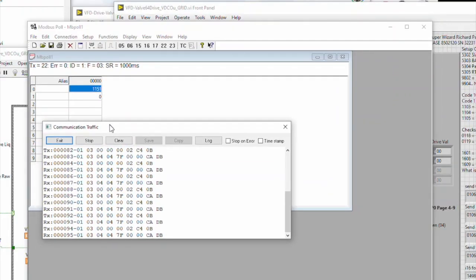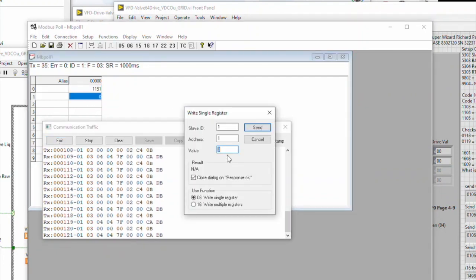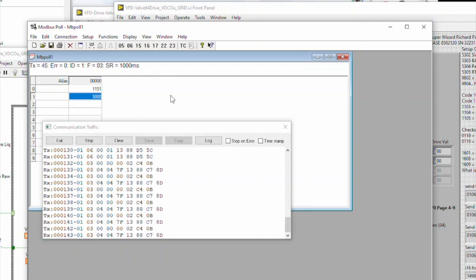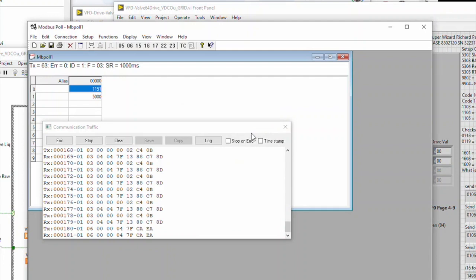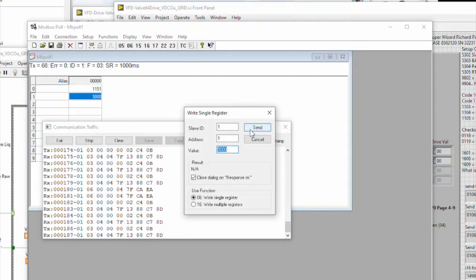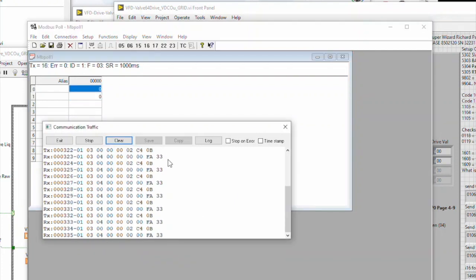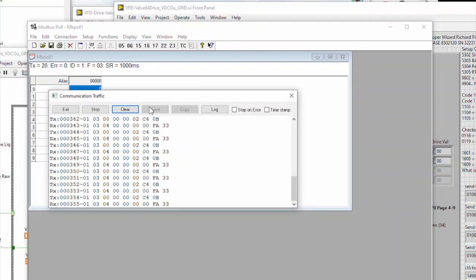And here's the communication traffic. You can see it's address 1, function code 3, and we've got a TX and an RX. And these are the CRCs. So I'm going to set this to 5,000. So we'll see that 5,000 be sent. You can pause the video and see what goodies are, and you'll see how it's set at 15 hertz. And now I'm going to set it to 0 and turn it off. Here's what 0 looks like. Some tricks to know: if you change parameters in 53 and 98, you need to cycle the power of the ACS 550, 510, whatever you're using.